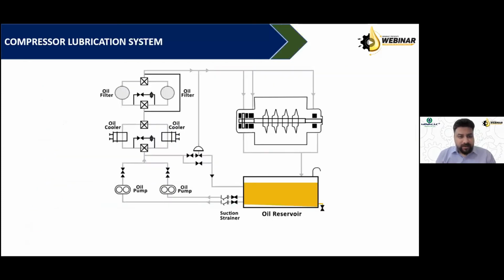There is a typical circuit for forced lubrication in case of a compressor. The circuit we have adopted here is for a dynamic type compressor, possibly an axial or centrifugal compressor, where the lubrication tank is totally separate. There is a video animation wherein you can see that the oil is taken in suction from the oil pumps. It goes into oil coolers. From there, it goes to certain duplex filter arrangements, then to the different bearings, and the return from the bearings comes back to the tanks.